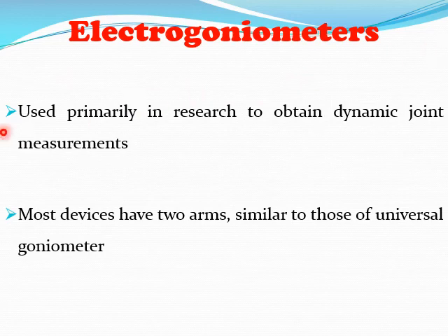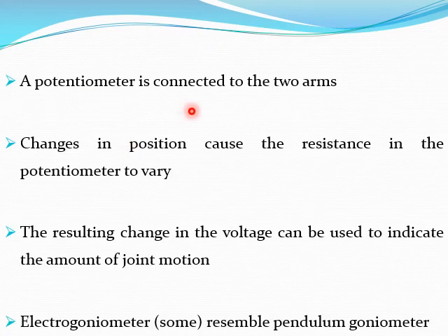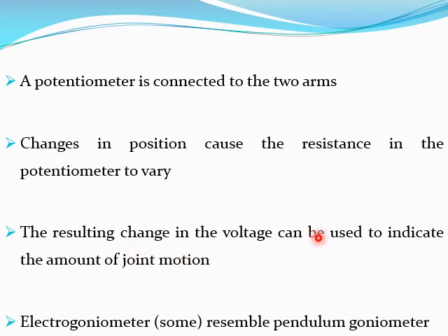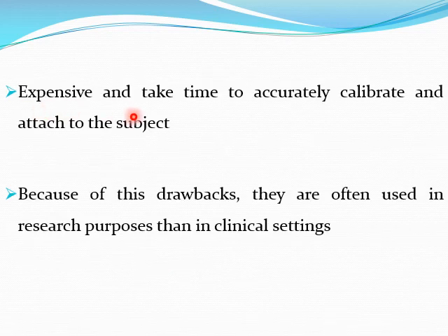Electrogoniometers are used primarily in research to obtain dynamic joint measurements. Most devices have two arms similar to those of the universal goniometer. A potentiometer is connected to the two arms, and changes in position cause the resistance in the potentiometer to vary. The resulting change in voltage can be used to indicate the amount of joint motion. Electrogoniometers are expensive and take time to accurately calibrate and attach to the subject, so they are often used in research settings.